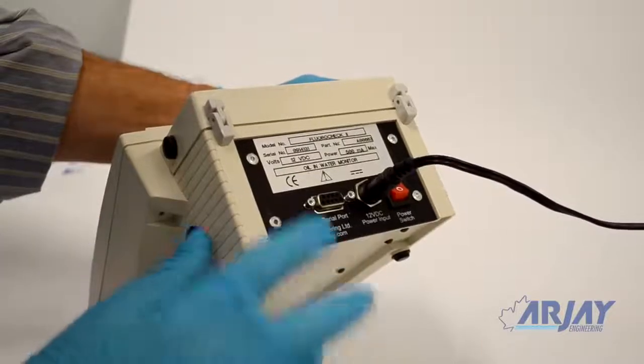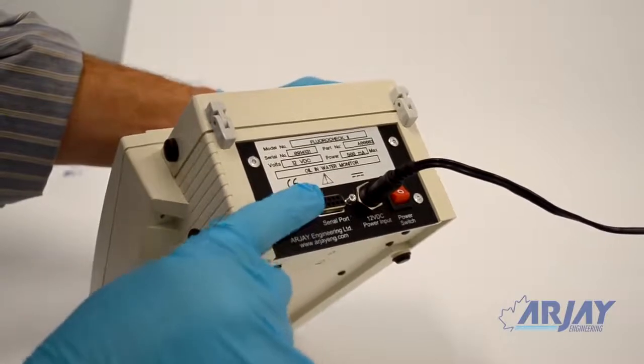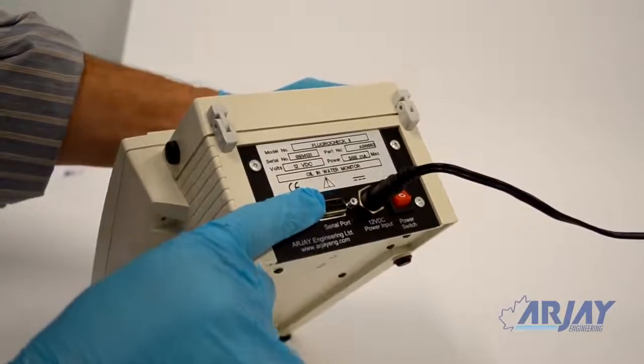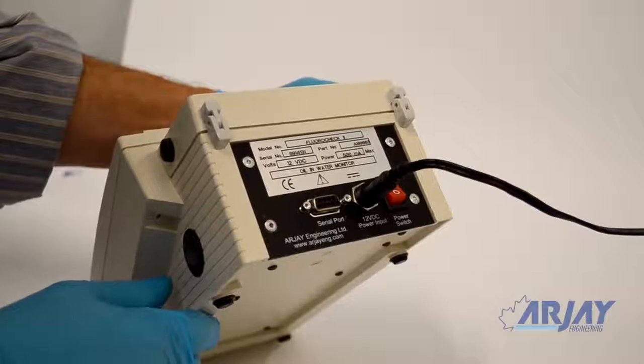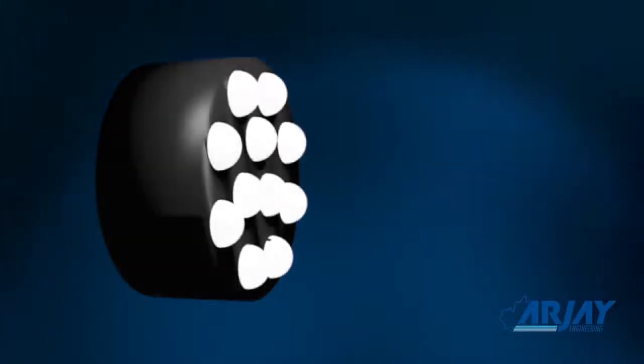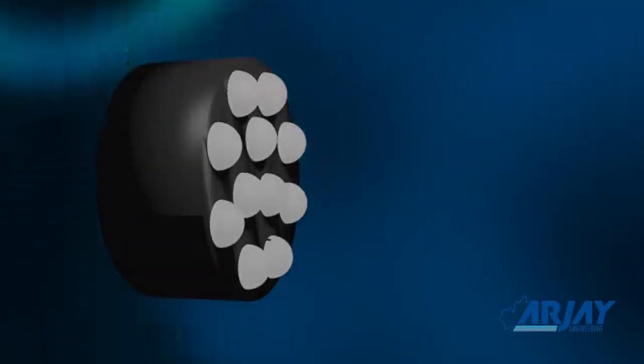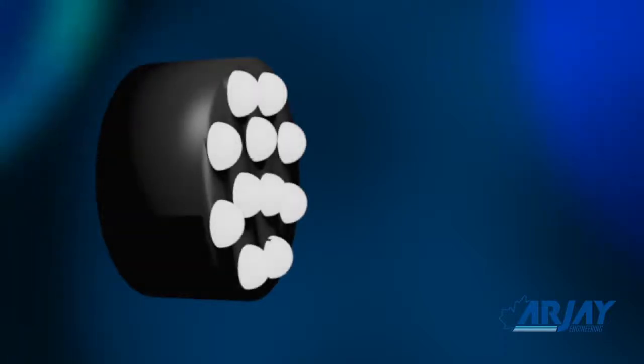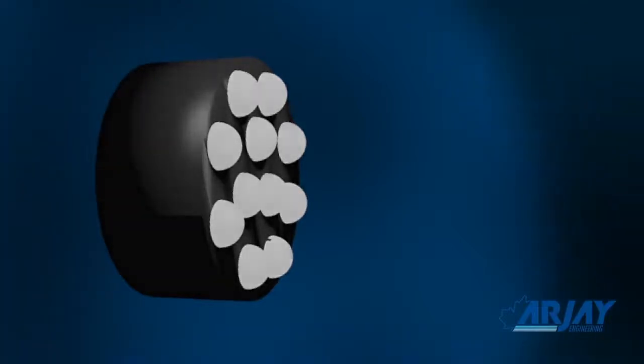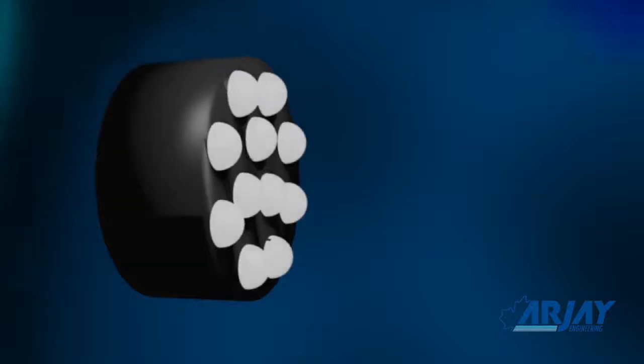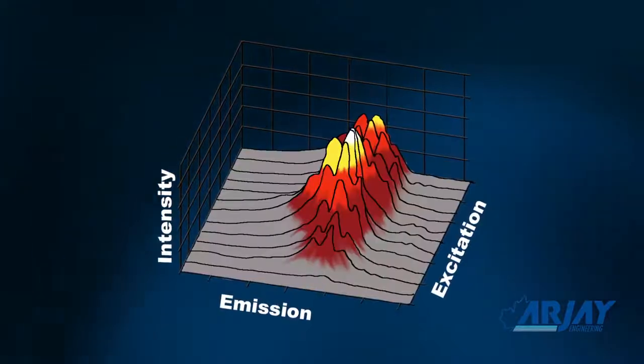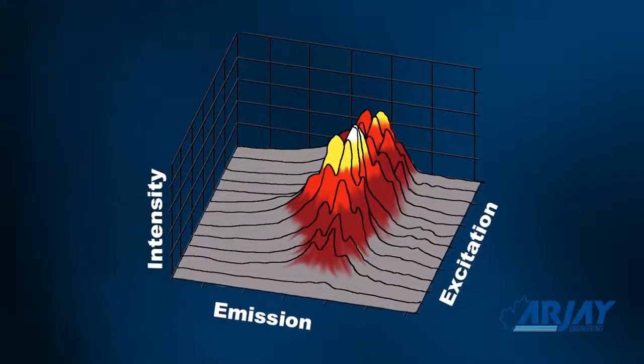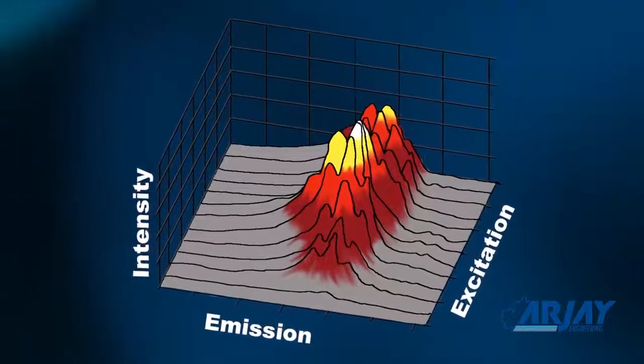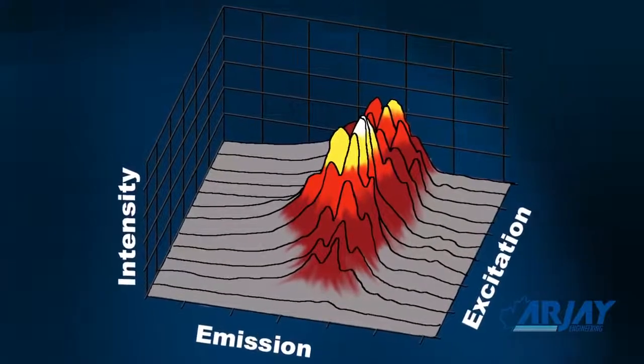An RS-232 port is provided on all instruments to download the information and your readings to a computer or printer for record keeping. The unique LED light cluster can be set to varying power strengths to optimize the fluorescence response of different oils. The unit will automatically turn off the LED source if there is an extended period of no activity. Since different oils can fluoresce at different intensities and peaks, the FluoroCheck allows up to 10 different calibrations to be stored in its memory.